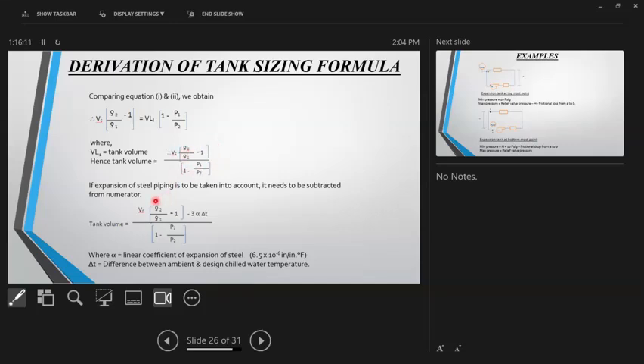Now here we didn't consider any steel expansion. We just talked about only water expansion. Because when temperature changes, piping also expands or contracts, and when piping expands, it helps to accommodate some of the water. So this is the term we will take from ISHRAE, that is, if expansion of steel piping is to be considered, you need to subtract that expansion, correct?